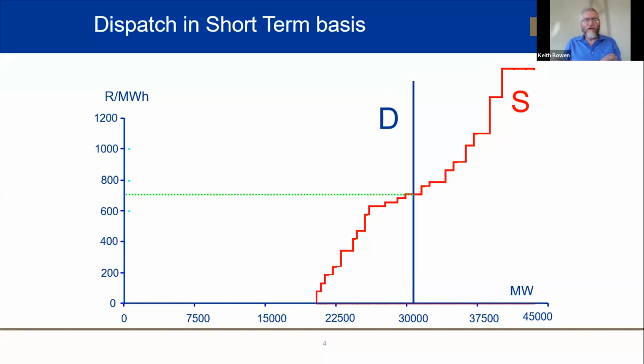Even going hour to hour there are constraints. Large coal power stations, even nuclear plants, have ramping capability, so they can't go from 100 megawatts to 500 megawatts in 10 minutes. That takes time, so a decision for one hour affects the hour before and after. Day-ahead optimization looks at least cost over the full 24 hours, so you might run a more expensive but more flexible generator in one hour so that both generators are available at their maximum during the peak. That co-optimization across different time windows has to happen on a day-ahead basis.